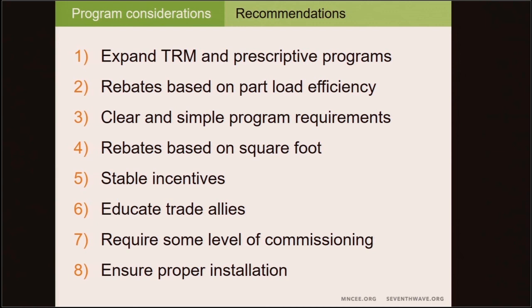Since expected RTU performance is often not achieved without proper commissioning, requiring some level of commissioning, such as its inclusion in contractor reports, will help ensure energy savings. Programs can also ensure proper RTU installation to achieve expected levels of performance. The Air Conditioning Contractors of America have developed guidance for proper installation. This standard also includes recommendations for owner training, which is important for ensuring persistence and high levels of energy performance and savings.